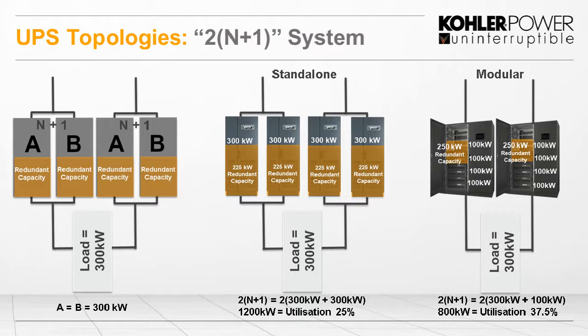But if we make it up out of smaller modules, we can put in less UPS, and in this example, we have 800 kilowatts, utilizing 37.5%. Now, it doesn't sound like much of a difference, but modern UPSs run efficiently over 25%. At 25% and below, they start to become quite inefficient. So the running costs have to be considered in these cases.